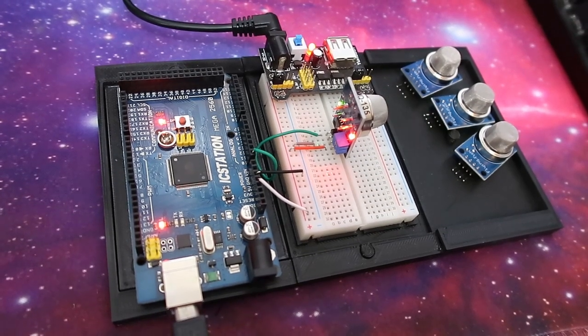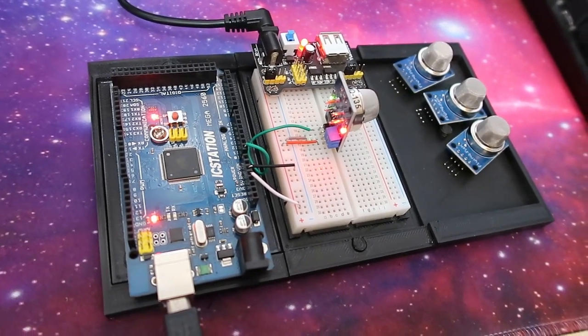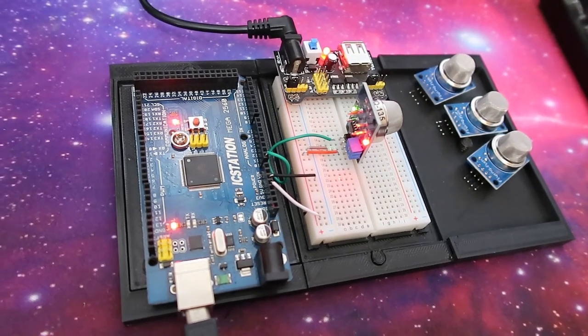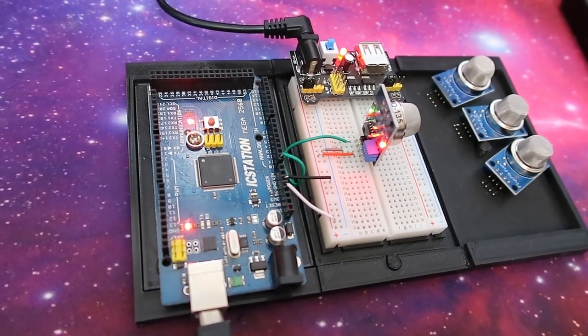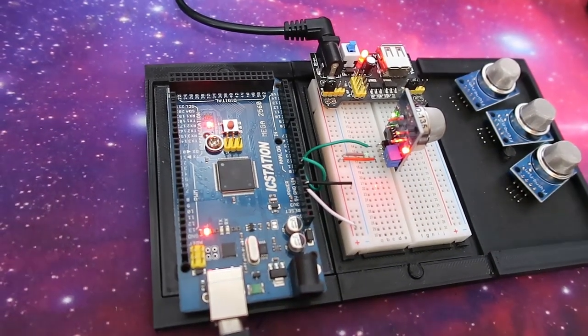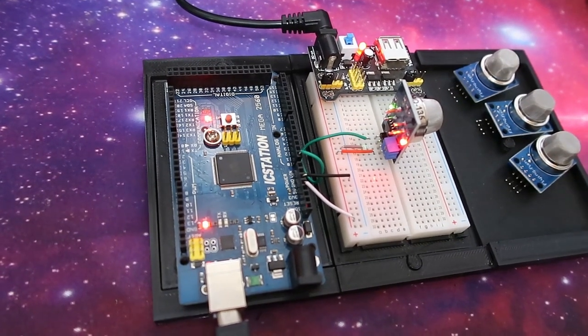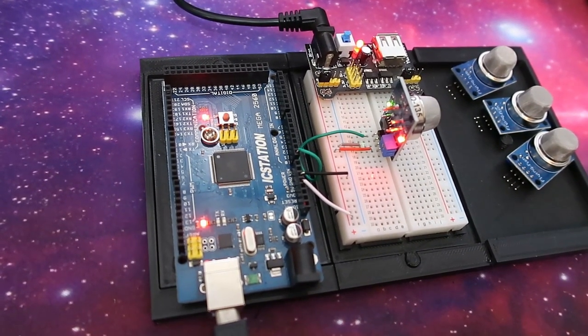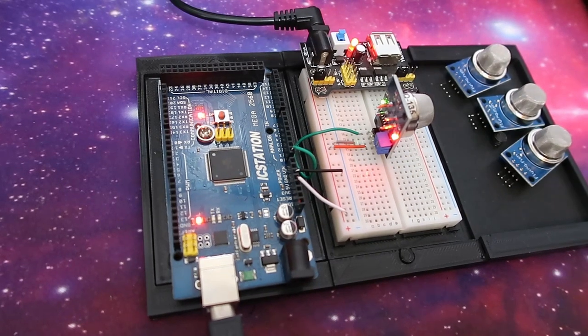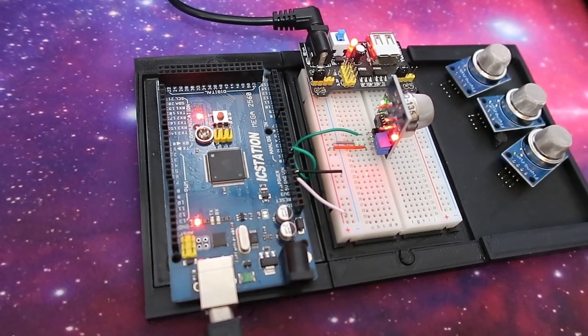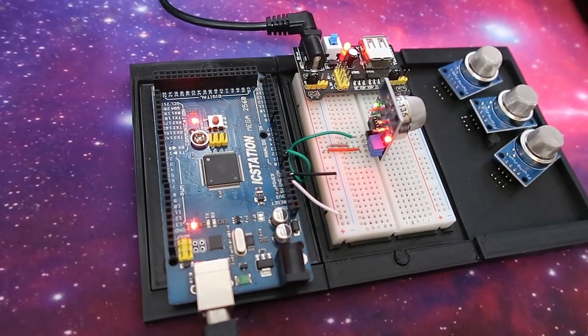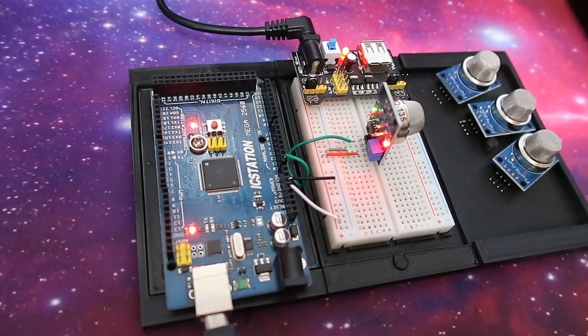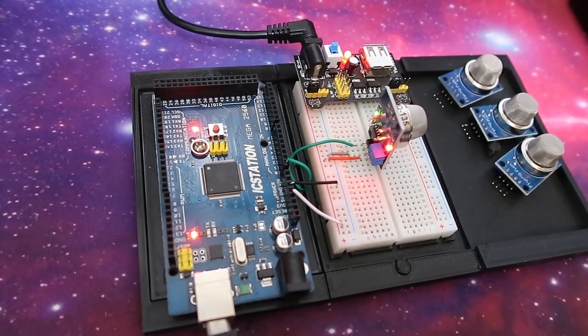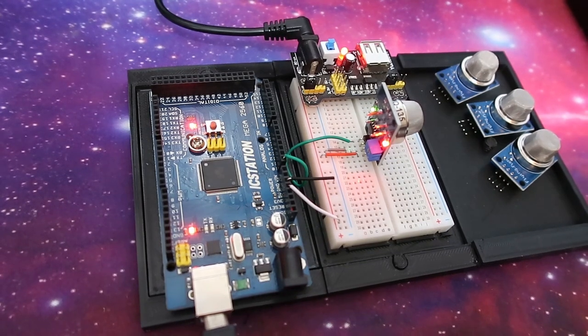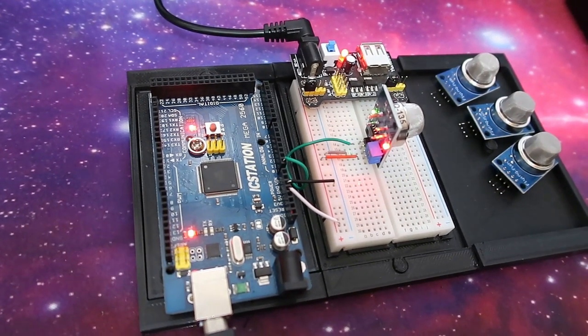You need to give it about 2 minutes to warm up, because it has a coil inside that needs to warm up inside the actual sensor. If you don't, you could get readings that are a little bit off. The other thing you need to realize is that these sensors need to what's called burn in, and you need to leave it turned on overnight for about 24 hours, so it actually adjusts itself from being a brand new sensor. That's just something you have to do with these sensors.